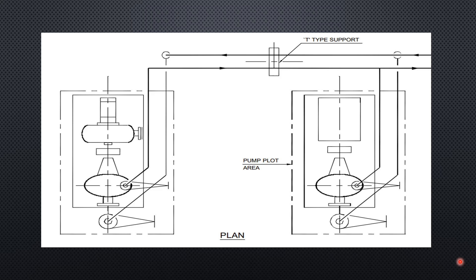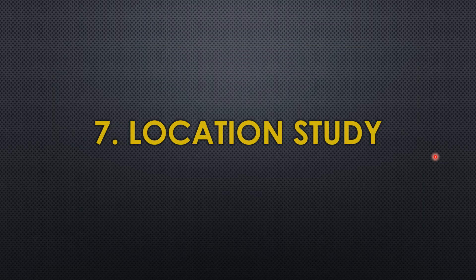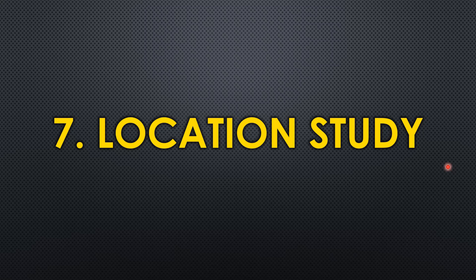The sixth parameter is support study. Before planning pump piping, you should identify nearby existing supports, because you can reuse them. Route the piping in such a way that reuses existing supports and avoids adding new ones. Evaluating nearby supports will help you create better pipe routing, reduce costs, and avoid unnecessary additional support structures.